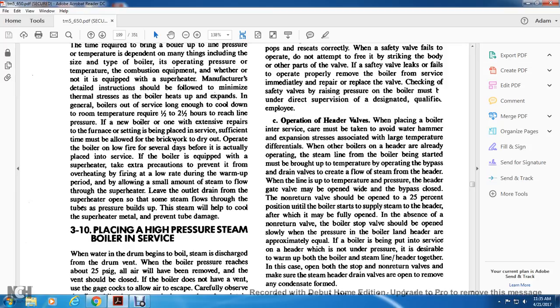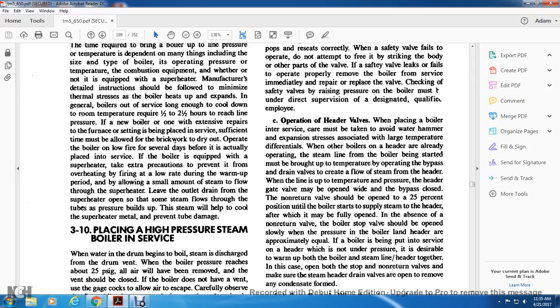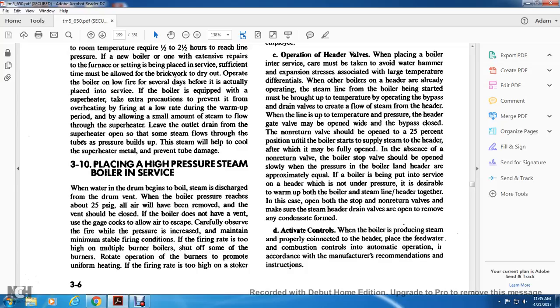Operation of header valve: when placing a boiler into service, care must be taken to avoid water hammer and expansion stress associated with large temperature differentials when other boilers are on a header or already operating. The steam line with the boiler being started must be brought to temperature by operating bypass drain valves to create flow of steam from the header. When temperature and pressure of the header and gate valve are equal, the valve may be opened wide. Activate controls: when the boiler is producing steam properly, connect it to the header, place feed water and combustion controls in automatic operation according to manufacturer recommendations and instructions.